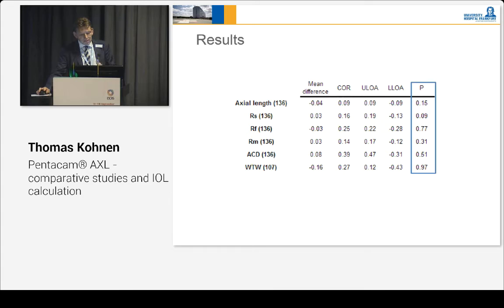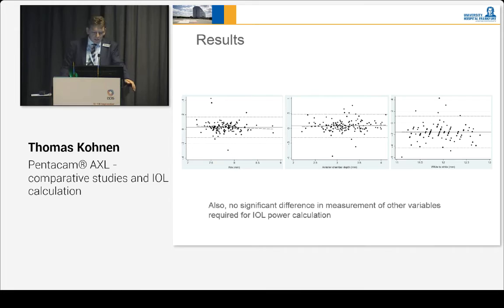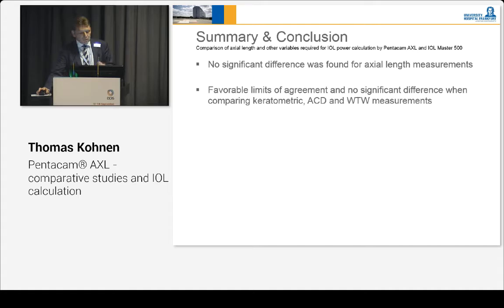Looking at the other variables, the results show a very good correlation in terms of the steep and flat meridians. The ACD anterior chamber depth was slightly different, as was the white-to-white measurement. Statistically, the limits of agreement are excellent, and no significant difference in measurement of other variables required for IOL power calculation was found. In summary, no significant difference was found for axial length measurement. Favorable limits of agreement and no significant difference were found when comparing keratometry, ACD, and white-to-white measurements. Lens calculation could probably be made with this device in the near future, with further research.